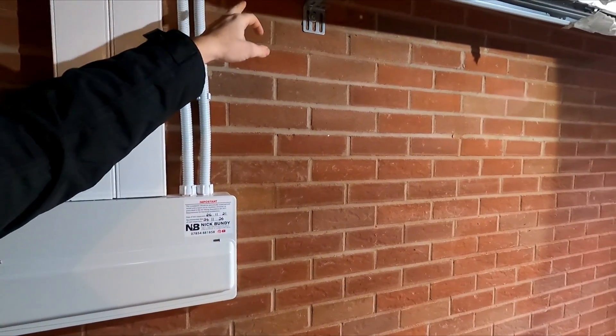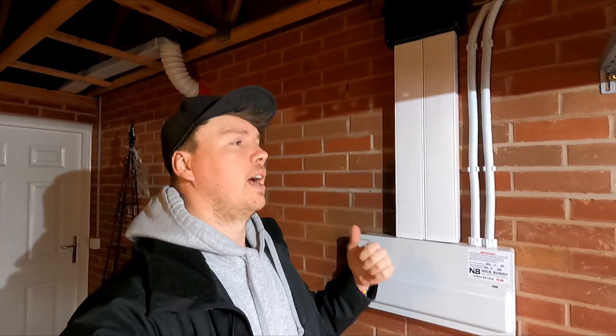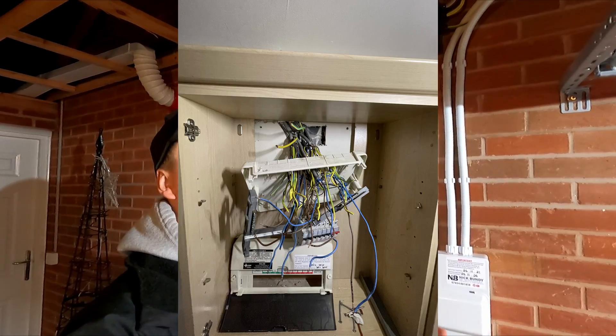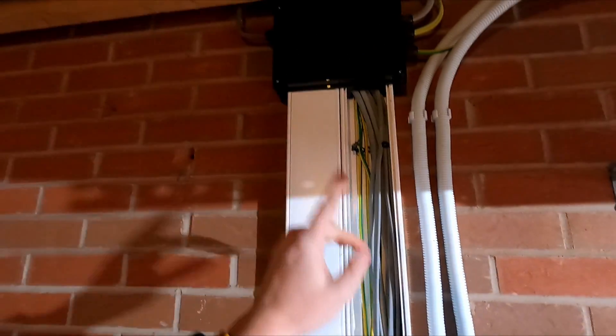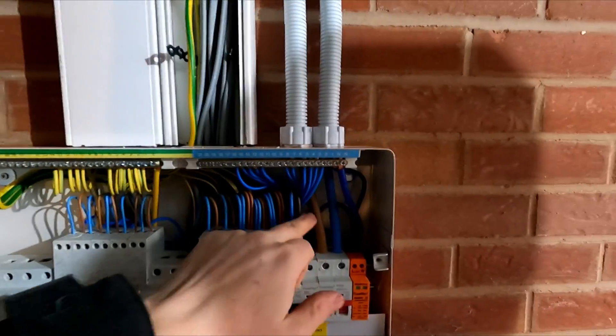We'll run a garage socket - there's one socket here which is a 20 amp. I'll pull the board cover off and show you what we've done, and at the end of the video I'll let you know the price I charged the lady. There were eight or ten spotlights we put in the kitchen. Now, when we removed the fuse board off the kitchen wall, there was no capping, no protection - the cables were just plastered directly into the wall, main tails and everything. Working really nicely though: directly above me are the floorboards above the kitchen. We managed to take the board off, pull all the cables into the ceiling space - Adam got the floor up above and every single cable managed to pull directly through the wall into an adaptable box above, giving us enough length to extend the cables and bring them down.